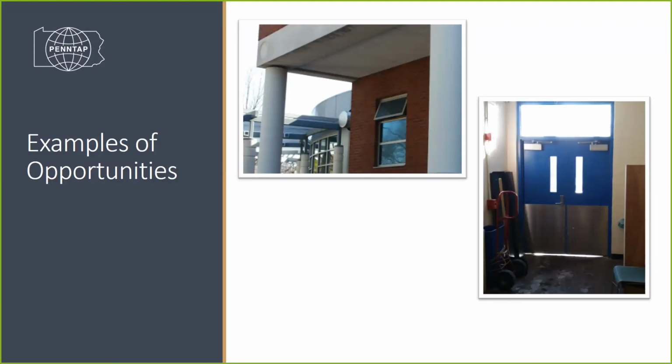This slide right here shows examples of looking at the building envelope. In the top left photo, there's a picture of a window open, and this is during the winter. This poses a question, of course, why? Why is the window open in the winter? So obviously it must be too warm in that area inside the building. So when you're in there, the room obviously is too warm. So further investigation is required. So what is the root cause?